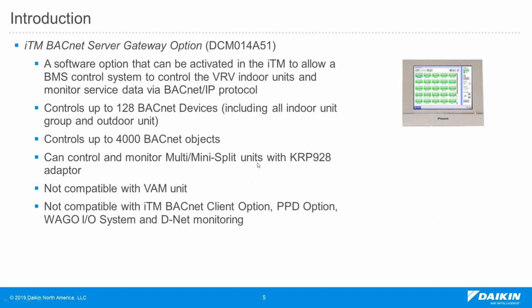The ITM BACnet Server Gateway, on the other hand, is a software option to control the VRV system. It can not only control the VRV system, but also monitor the service data from the VRV system via the BACnet IP protocol. So it can control up to 128 BACnet devices. One indoor unit group is counted as one BACnet device, and one outdoor unit is counted as one BACnet device. So the total number of the indoor unit groups and the monitored outdoor units should be less than 128 for one ITM gateway option. The capacity is also limited by the total number of BACnet objects. So when you are commissioning this ITM gateway, it is necessary to choose which BACnet objects you would like to expose to the BMS, and the maximum number of BACnet objects you can control is 4,000.